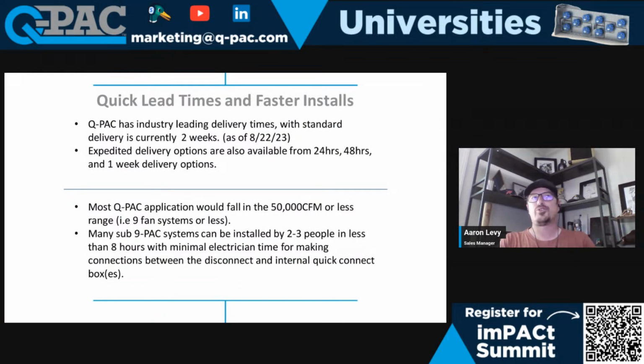We touched on this earlier about lead times and installation times. This does tend to be the biggest selling point, not just from the redundancy side of it, but when we're looking at lead time when things fail. Depending on our competition or any other type of application, when you're looking at new pieces of equipment, you're anywhere from 8 to 10 weeks to maybe 20 to 30 weeks for a brand new piece of equipment. And that's stuff that, when something fails today and they need something tomorrow, that's not really a viable solution.